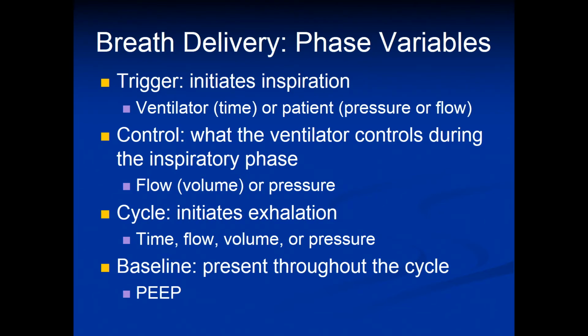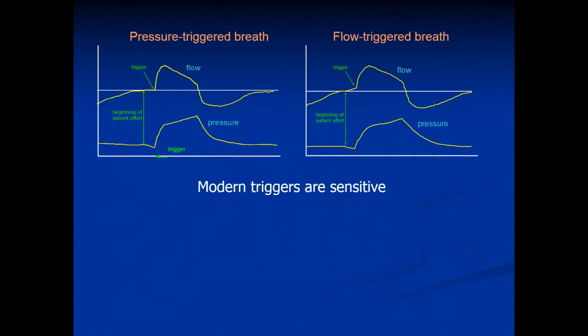The cycle, or initiation of exhalation, can be done based on time, flow, volume, or pressure. And again, the baseline can either be set at 0 pressure or at a certain PEEP level. Every breath will begin and end at the same level that is the baseline. In this picture, you can see pressure-triggered breaths on the left and flow-triggered breaths on the right. You can see in the tracings on the left that inspiration begins when the pressure drops to a certain preset level. On the tracing on the right, the ventilator waits to see an elevation of flow for the initiation of the breath.